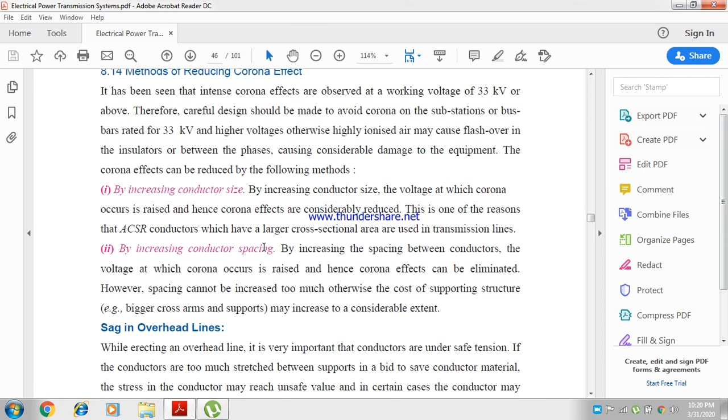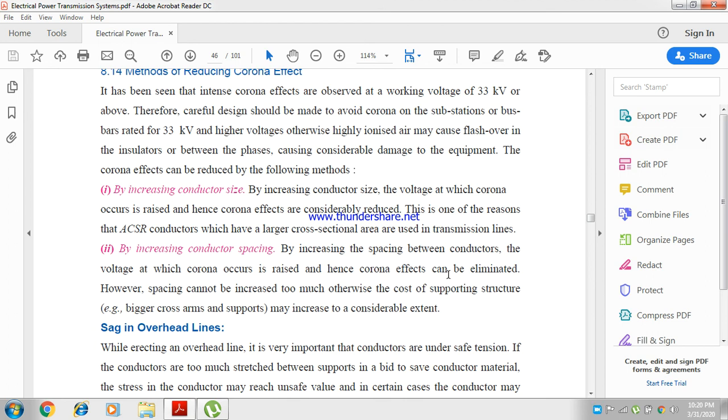By increasing the conductor spacing. By increasing the spacing between the conductors, the voltage at which corona occurs is raised and hence the corona effects can be eliminated. However, spacing cannot be increased too much, otherwise the cost of supporting structures may increase to a considerable extent.